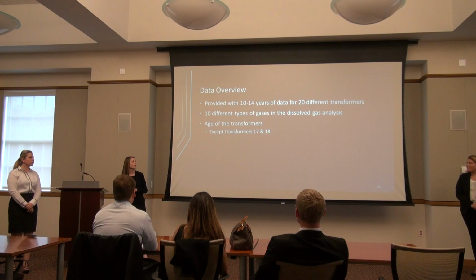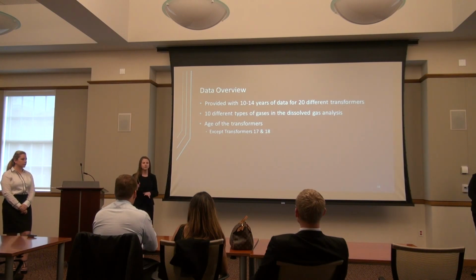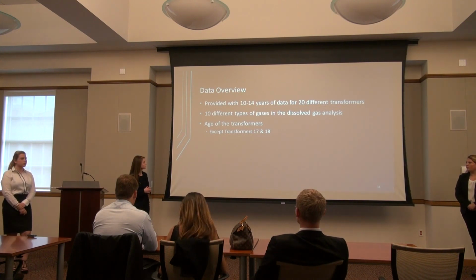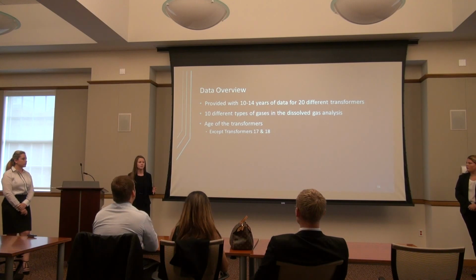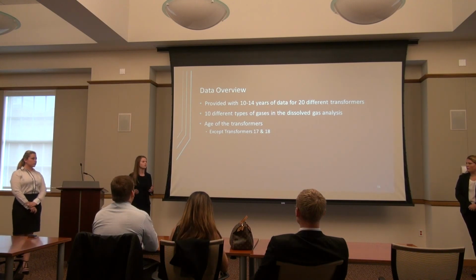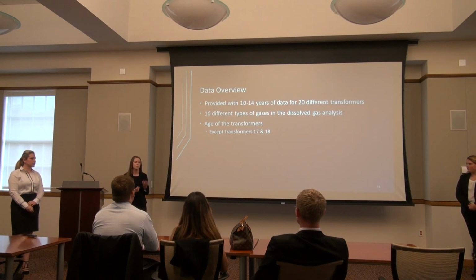So the data that we were provided with was about 10 years of data per transformer with 20 transformers. So this gave us about 200 counts of data from different tests that have been done on the oil in these transformers. Additionally, for each test, there are 10 different gases that we were given the amount of at that particular time that's in the transformer. We were also given the age of the transformers except for numbers 17 and 18. So we were missing those pieces of data for those two transformers.